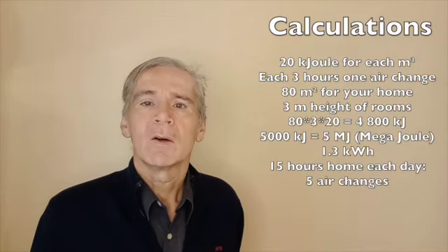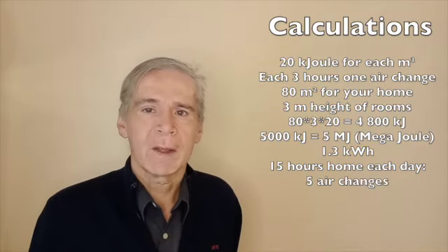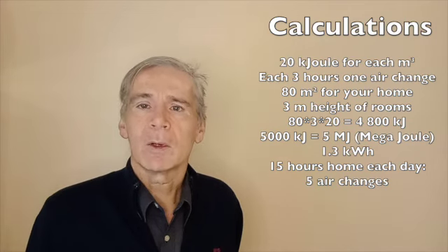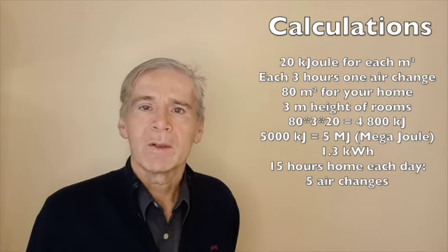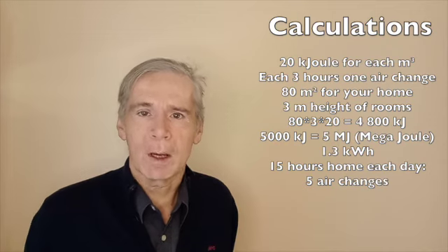So you need these 20 kilojoules for each cubic meter of your home, and that's maybe 240 times 20, or nearly 5000 kilojoules, that's 5 megajoules, or 1.3 kilowatt hours for an 80 square meter house. And that's each 3 hours. If you do that for 15 hours per day that you're home, you already need close to 1 cubic meter of natural gas per day for only this heat loss, without counting other losses.